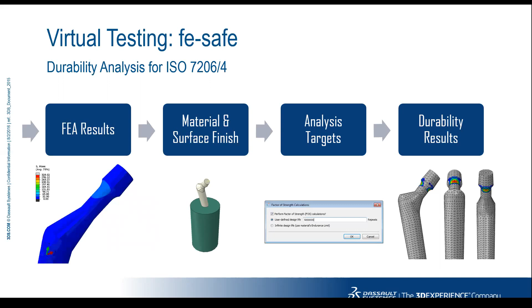In this case, the loads used are a simple sinusoidal load as defined in the standard, and the material used is a medical grade titanium alloy. To pass the certification, the implant must sustain 5 million repeats of sinusoidal load. And as you can see in the picture, the critical area is typically located at the neck of the implant, just below the taper. Right? Okay.